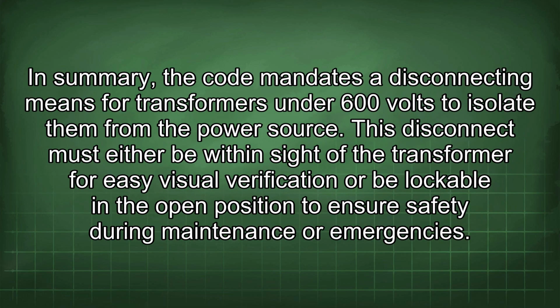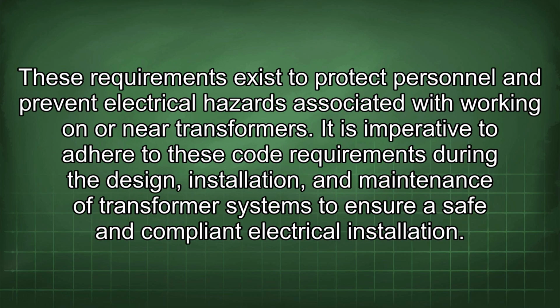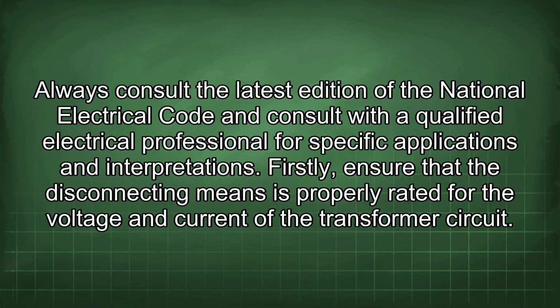In summary, the code mandates a disconnecting means for transformers under 600 volts to isolate them from the power source. This disconnect must either be within sight of the transformer for easy visual verification or be lockable in the open position to ensure safety during maintenance or emergencies. These requirements exist to protect personnel and prevent electrical hazards associated with working on or near transformers. It is imperative to adhere to these code requirements during the design, installation, and maintenance of transformer systems to ensure a safe and compliant electrical installation. Always consult the latest edition of the National Electrical Code and consult with a qualified electrical professional for specific applications and interpretations.